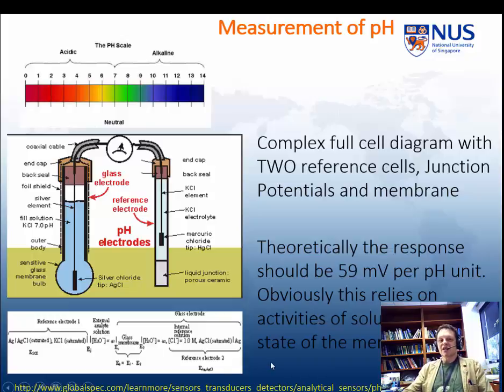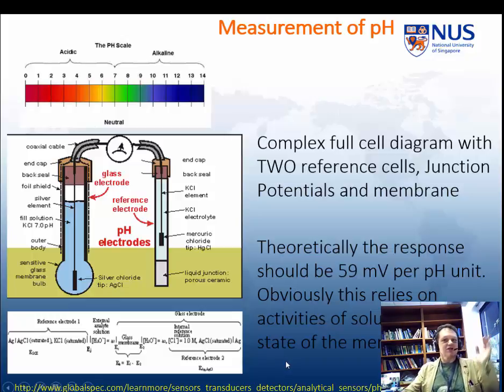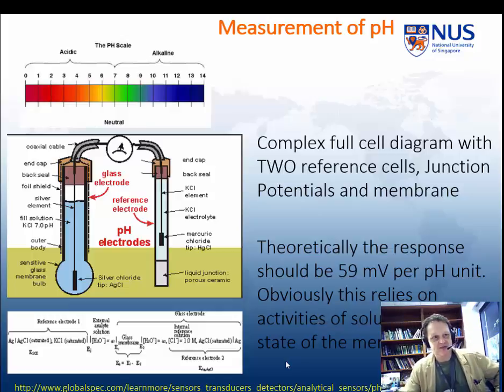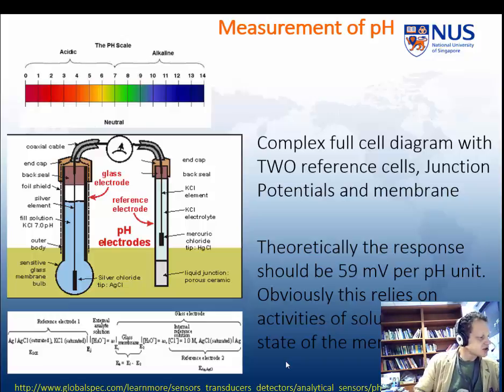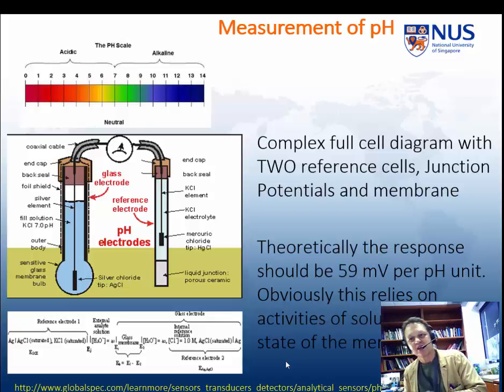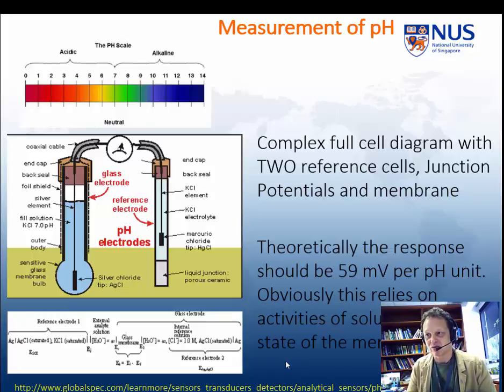As with all single ion electrodes, the potential difference across that membrane is actually what you're interested in. This glass membrane is not your typical window glass, as you're aware. There are a range of pH glasses which have these specialist properties. A general robust one might be 22% sodium oxide, 6% calcium oxide, and 72% silicon dioxide. They're engineered around that because hydrogen ions need to be permeable through that membrane — or at least it's actually an absorption phenomenon on both sides.